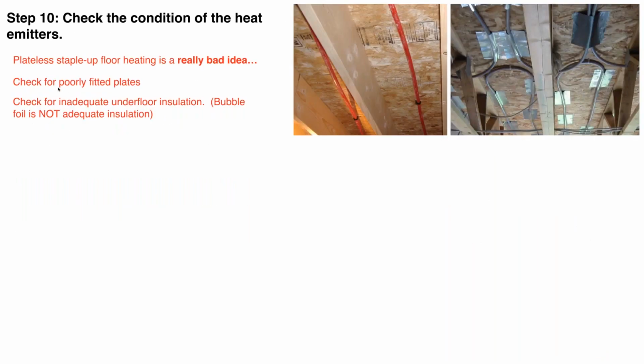Check condition of heat emitters. Here's what we call plateless staple-up. Really bad idea. I've seen many examples of this where somebody assumes just putting the tubing next to the floor is good enough, and putting some bubble foil or putting some site-built plates over it. These are just very, very inadequate heat transfer paths. You're just never going to get proper performance for that.